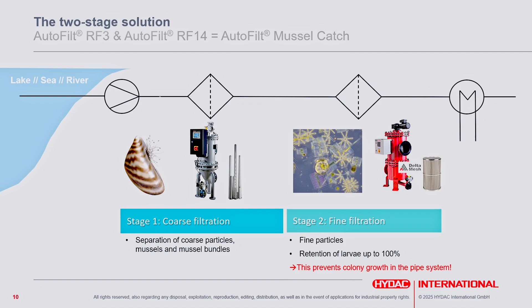In this schematic, on the left side we have a lake, sea, or river, and on the right side a consumer, in this example a heat exchanger. The theory is: if we take water from this lake or sea, we use a filter cascade—the RF3 for separating coarse particles, mussels and mussel bundles, and the fine filter, the RF14, for fine particles, retaining the larvae up to 100%. This prevents colony growth in the pipe system, and in our opinion, is the only economic and working solution without any downtime in the customer's system.